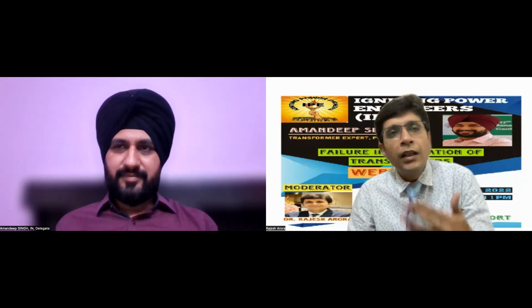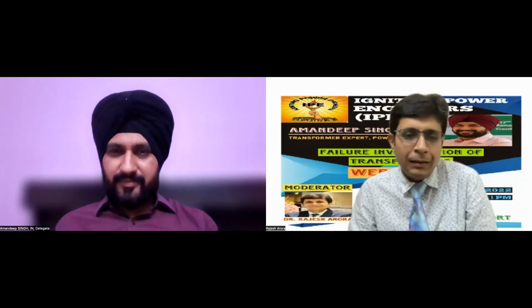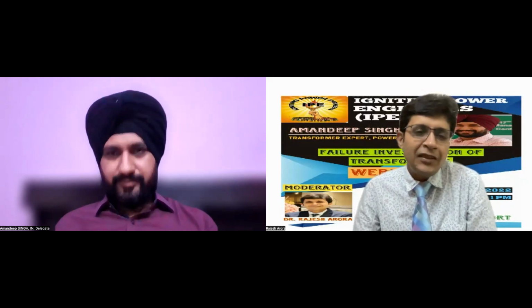Okay. Now, coming to the last slide, you have mentioned you are using the alternative oil, natural ester oil, and that helps you to bring down your failure rate. But I have one very simple question. When you are using natural ester oil in your transformer or reactor, how do you take care of the OLTC and the cooling settings? Meaning when to start the fan, because the temperature is comparatively higher as compared to mineral oil. In that case, what should be the OTI and WTI setting?